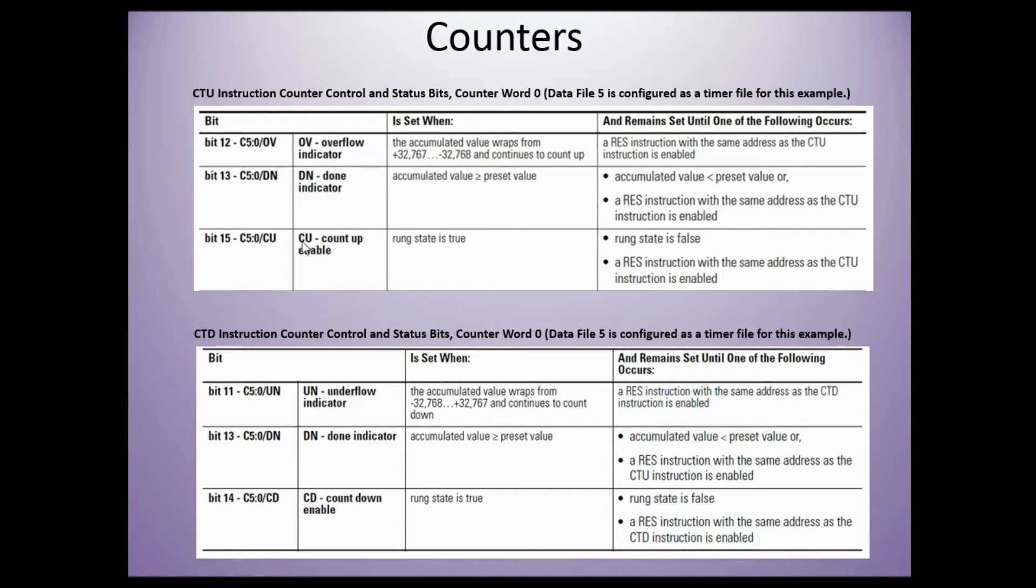With a CTD counter, your countdown counter, bit 11, the UN bit, is set high when the value wraps from negative 32,768 to positive 32,767 and continues to count down. A reset instruction is needed in order to set that bit low again because it is retentive.